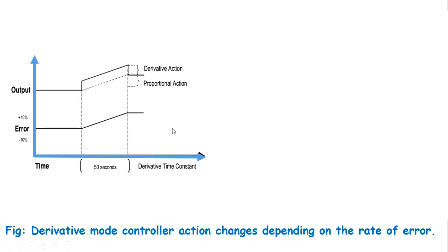In essence, it applies the brakes on the process error by quickly shifting the proportional band. Derivative has no effect on output if the error is not changing.